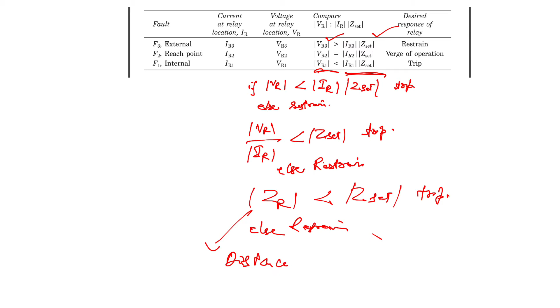Now the relay therefore has to compute the impedance as seen from this location and compare it with the set value to take the trip decision. Because of the simple series model of the faulted line, the line impedance is directly proportional to the distance, and so the name distance relay. So we can call it the distance relay.